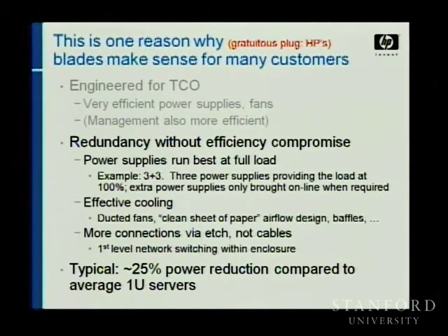Blade systems, at least ours, but I would assume other folks can do this, will run as many supplies as is necessary to power the load, and the other ones are in hot standby. And so in one AC cycle, they can bring those on if they're needed, if another power supply fails, or if somebody's running LinPack and all of a sudden the power draw goes up.